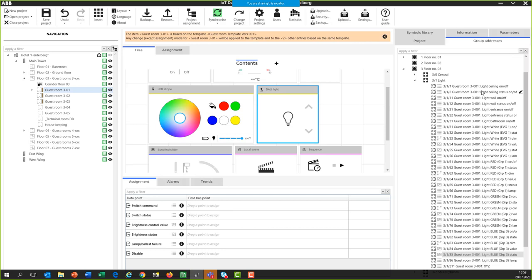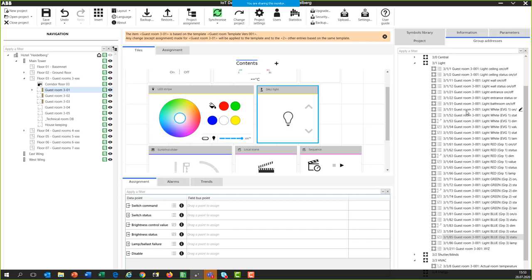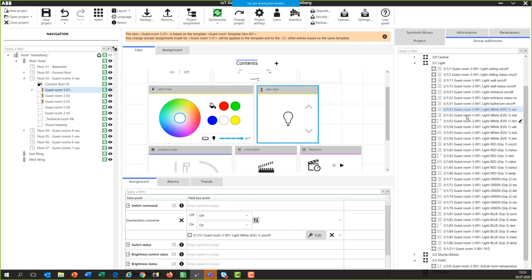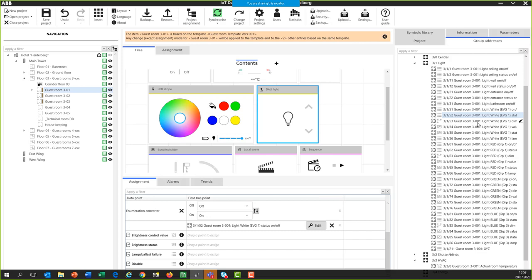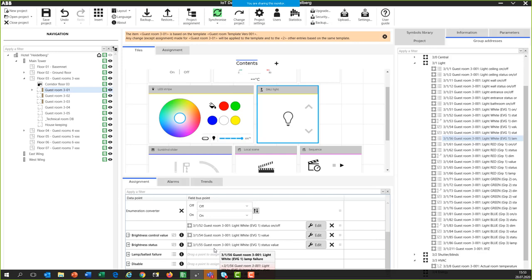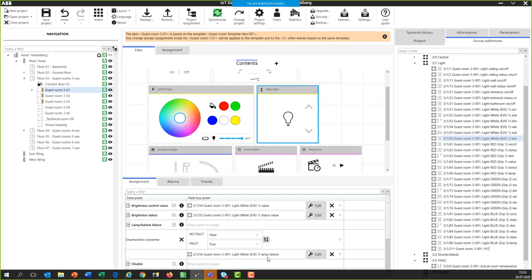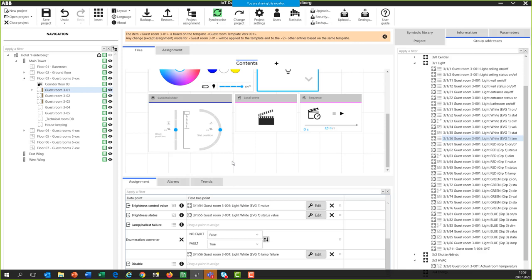For the DALI control element to switch and dim DALI ballast number 1: clicking on it reveals objects for switching, status, brightness, brightness status, and also lamp or ballast failure. I link the group address for switching to the switching object, the status group address to the status object, the brightness value and its status, and finally group address 3/1/56 — which is the lamp/ballast fault from the DALI gateway — to the lamp failure object.